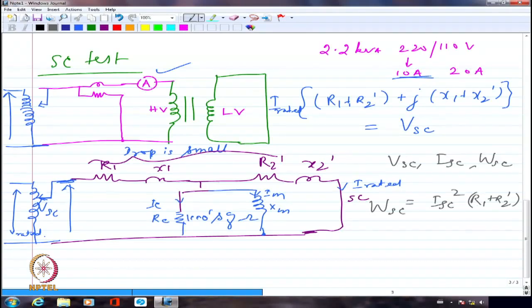Generally, it is very difficult to separate out R1 and R2 dash. Similarly, it is very difficult to separate out X1 and X2 dash. Most of the time, we take the total resistance divided by 2 as R1. Similarly, total resistance divided by 2, we'll take as R2 dash, which is okay for all practical purposes. Right? If I had measured the resistance of the primary winding right at the inception stage, then it is different. Otherwise, R1 and R2 dash, similarly X1 and X2 dash, would be very difficult to segregate. I would only get the total value, so I may call this R equivalent.